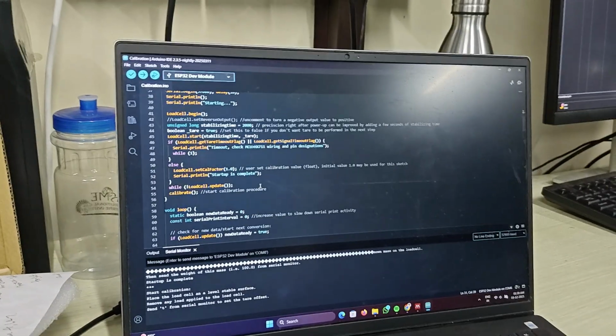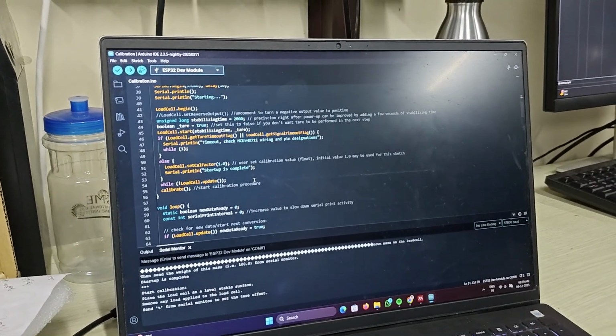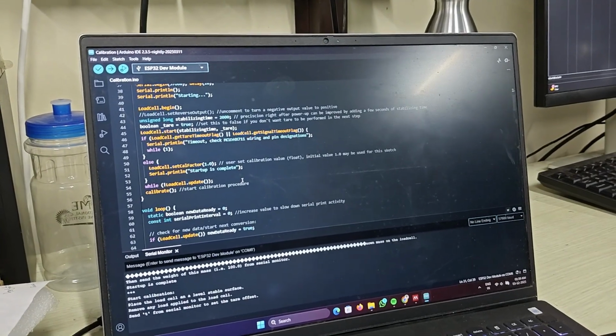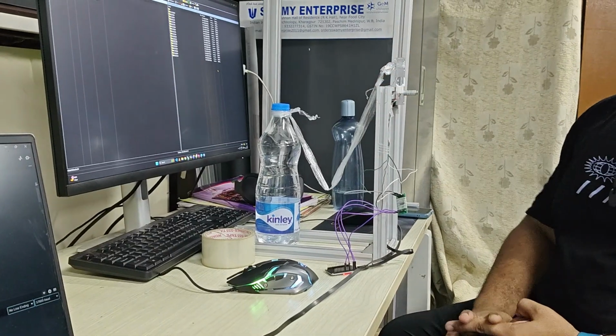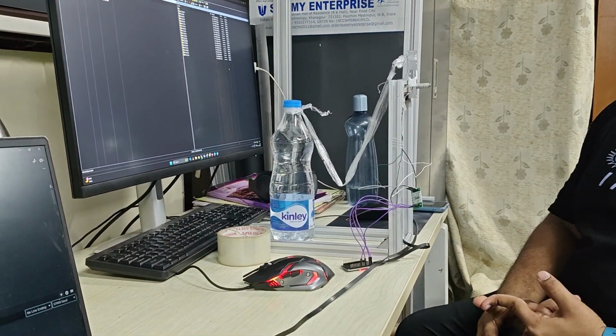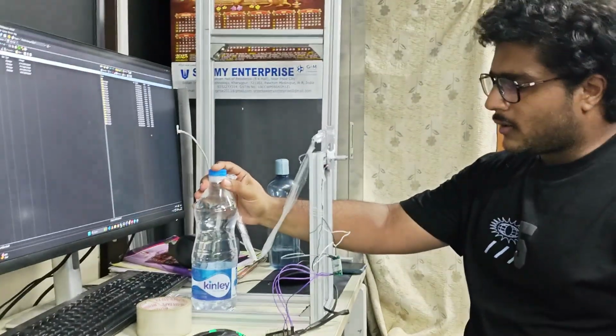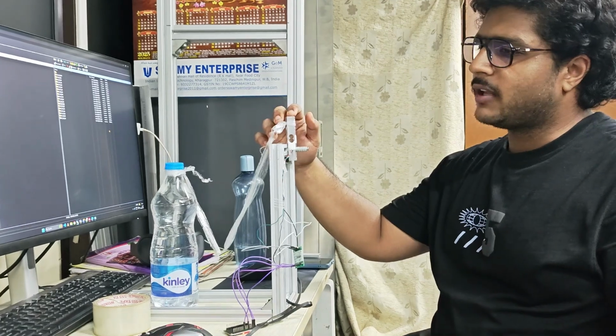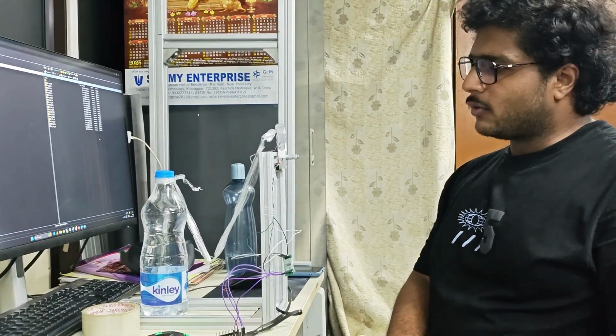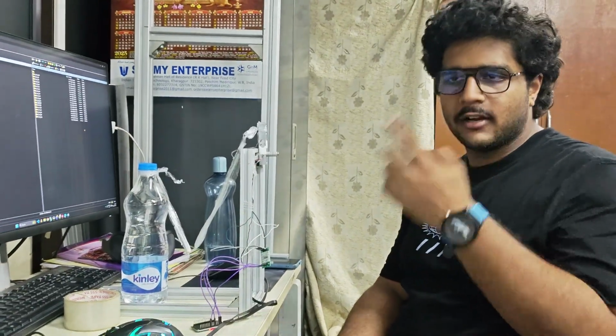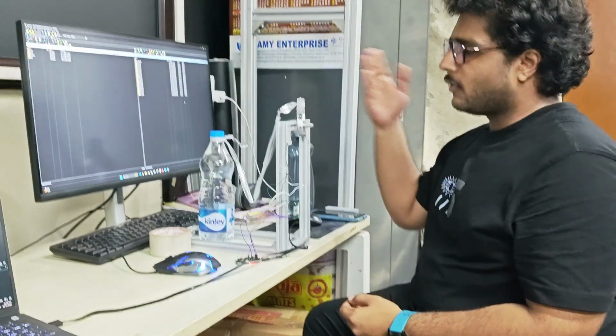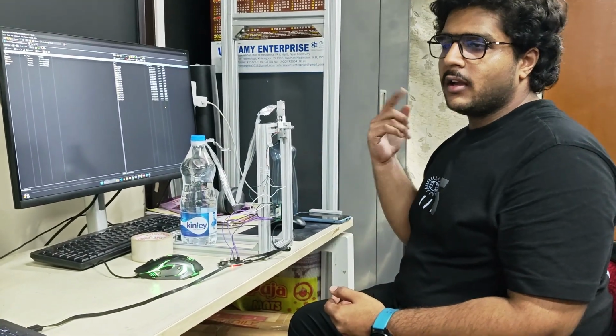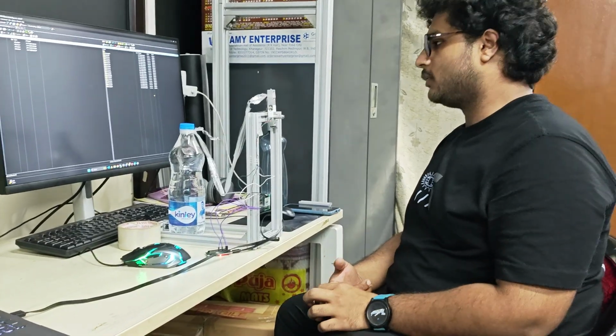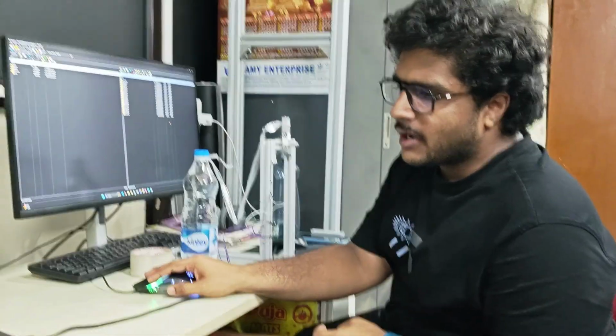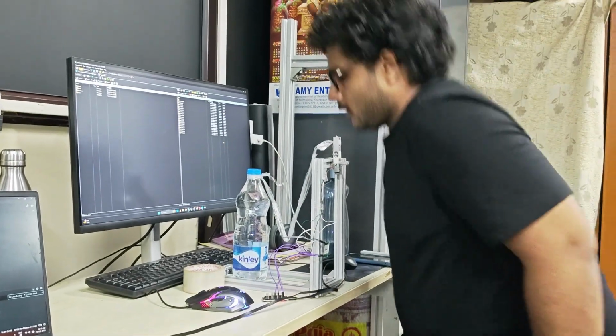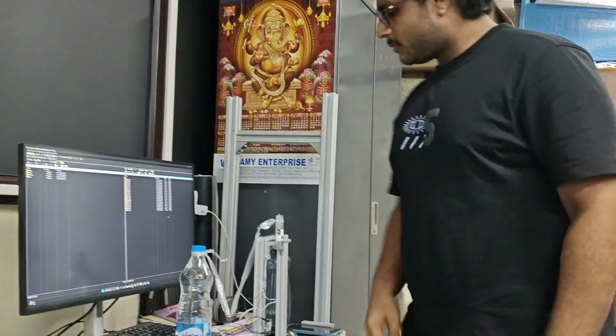Initially, we will tare the load cell to zero value, and with a known weight of 1000 grams, we will set the electrical signal value for 1000 grams as some fixed value, and as the deflections and bending of the load cell are happening in the elastic region, the forces will be proportional to displacements linearly, and hence for any other unknown weight, a linear interpolation can easily be used to find the force. So we will begin with the calibration process right now, and in the calibration process, the first step is to tare it.